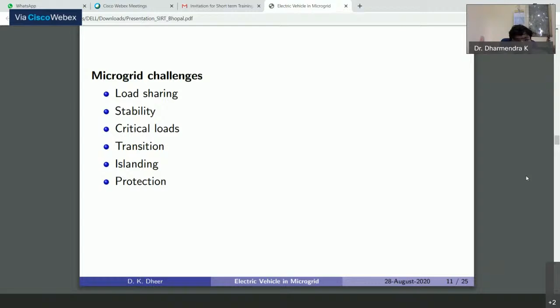The main challenge is the fault current level. Sometimes it increases, sometimes it decreases. So there should be something automated, which knows that these many generators are there at these locations, so for relay 1, relay 2, relay 3, this will be the fault current. This kind of provision should be there. If it is not there, then protection is still a challenge. Even nowadays, the protection of islanded microgrid is still an area where research is going on. Please, next slide.